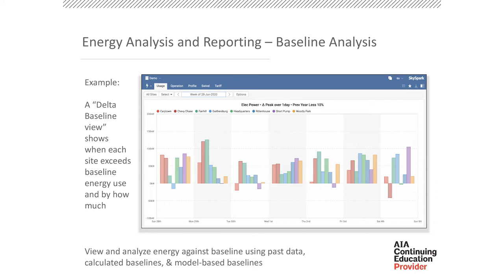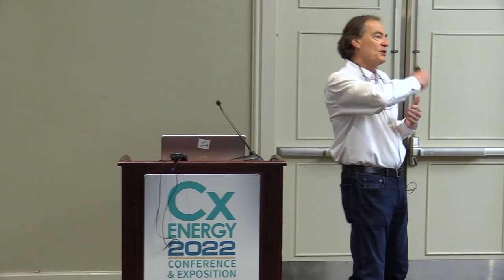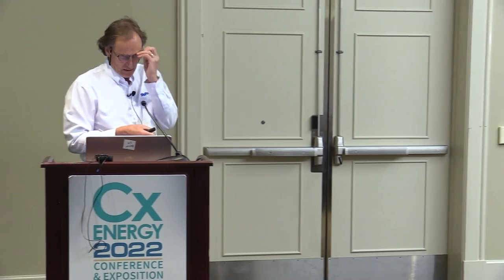All right, so the next one I want to talk about is baselining analysis. Baselines have a specific meaning, and then there are benchmarks, and then there are goals. But we're really talking about comparing against a set of data that we care about. It's the benchmark from the industry, the baseline from last year, or the goal for next year. It's basically the same concept when you're doing analytics, so we can compare against our baselines over any period of time. But we can also provide math. Let's compare against last year's data minus our goal, 10%. So we should look at our actual against our goal, which is based on what we committed to: we'll reduce demand or consumption by 10%. That's just an example of how we can present that as well.